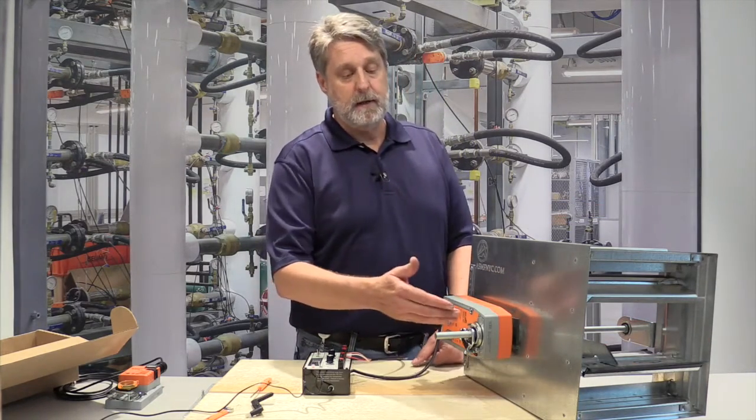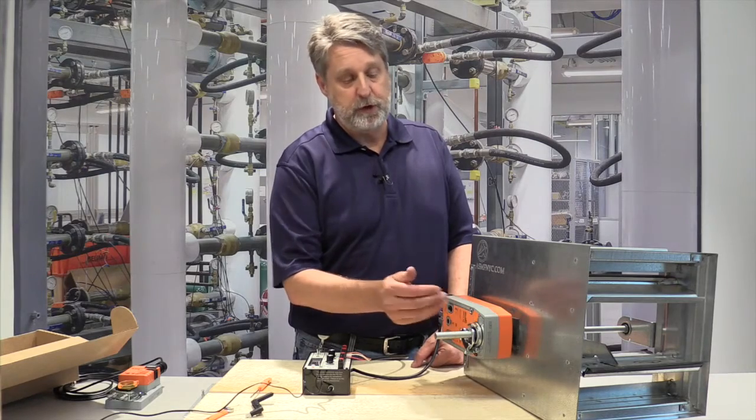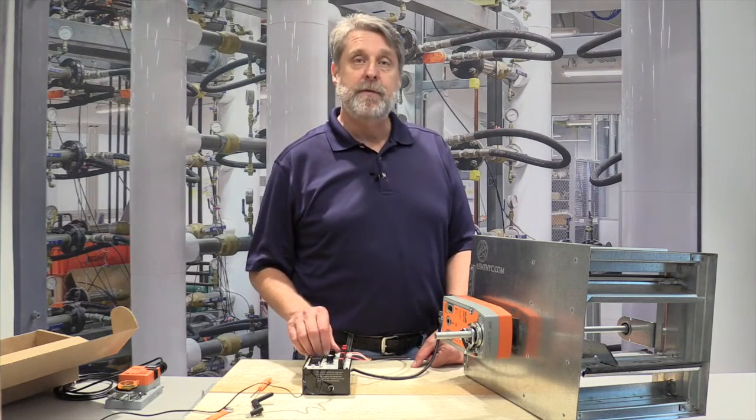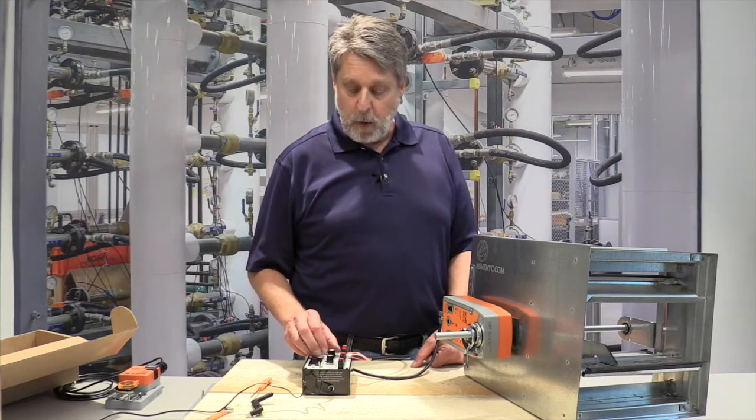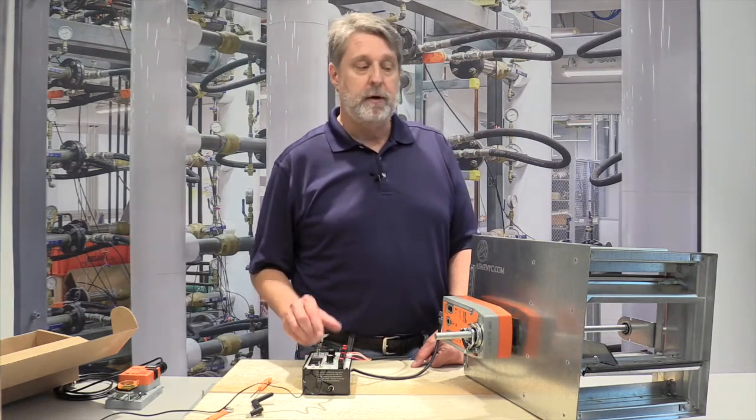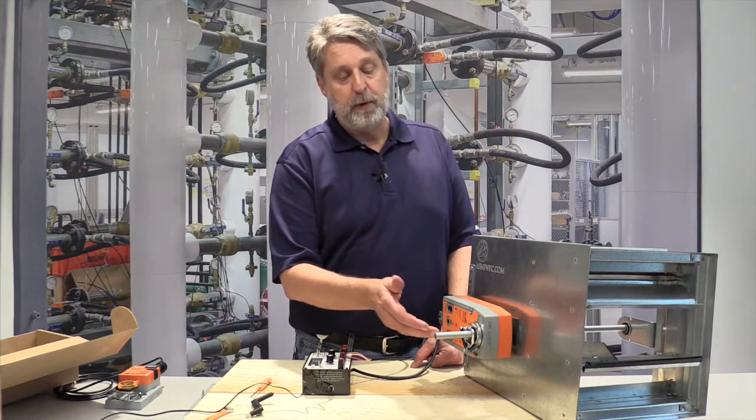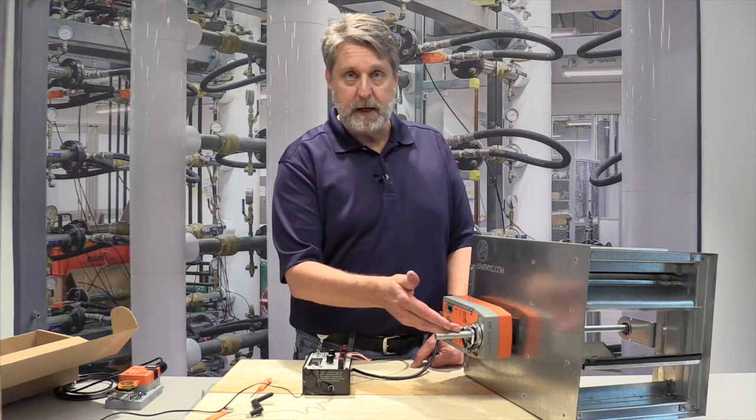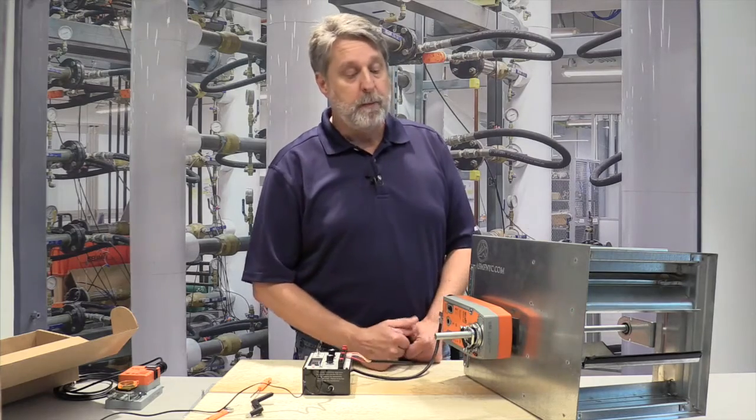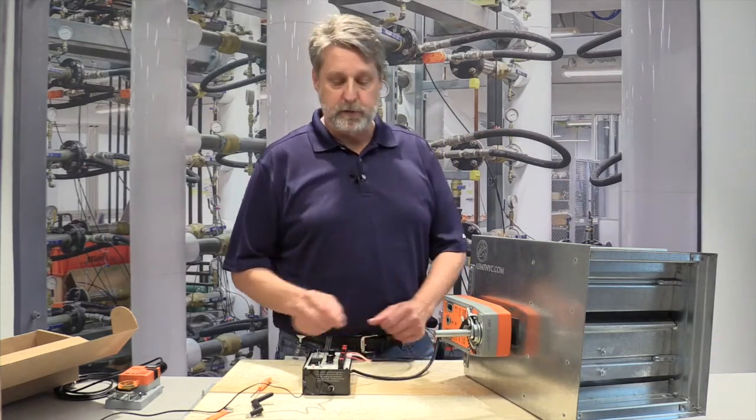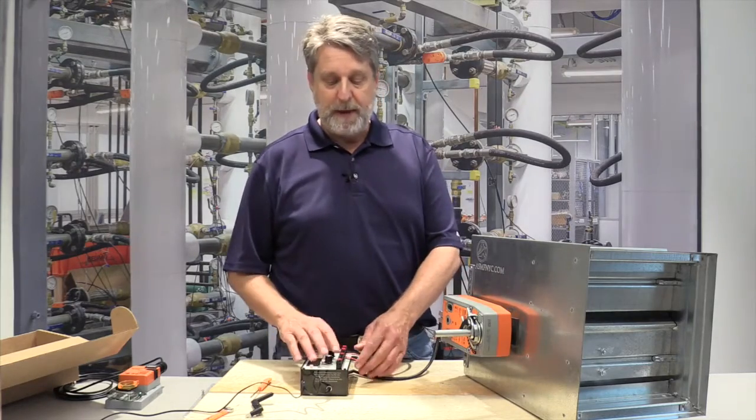Okay, the actuator has moved to the full open position. Everything looks good. I'm going to give it a two volt signal. I'm going to watch for the actuator to close, watch the damper assembly, look for smooth operation, make sure the shaft is spinning correctly and there's no binding. Okay, the damper has moved to the full closed position. Everything looks good. I'm going to turn off my power supply.